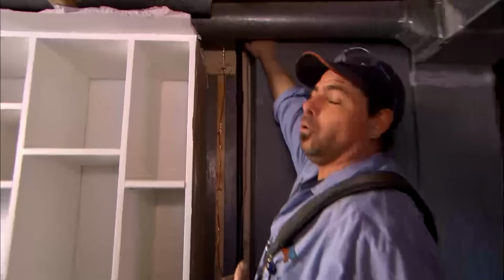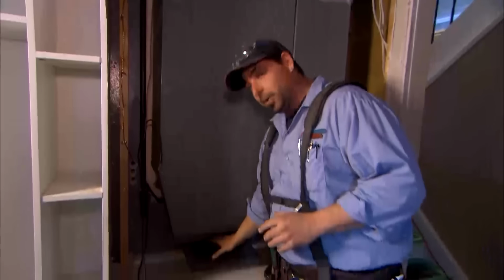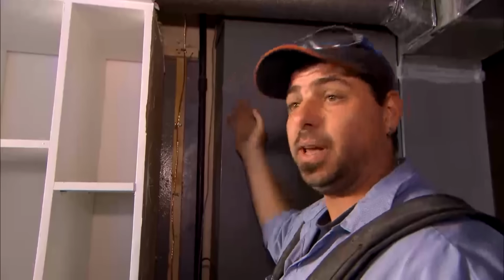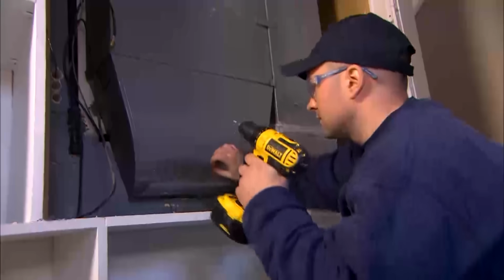Also, when we were taking this off, we found that the return is open up in this joist cavity, and there's another one open in a cavity with a gas pipe. That's not a good mix. Right now we've tested it and it's not leaking, but if it does leak, there's a possibility of gas getting drawn back into the return and into the furnace, which is potential for an explosion. So we'll get these all closed off and sealed up so nothing's leaking.